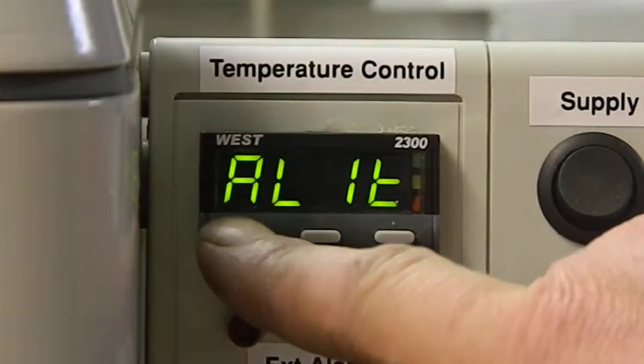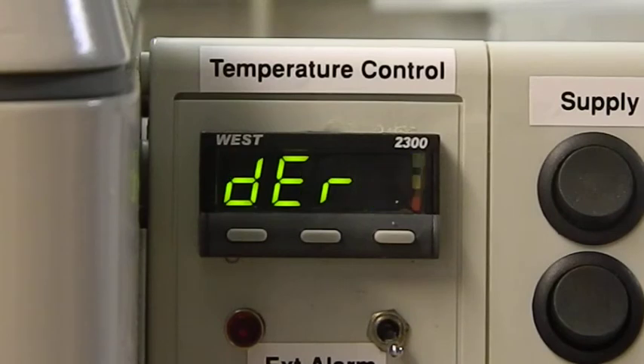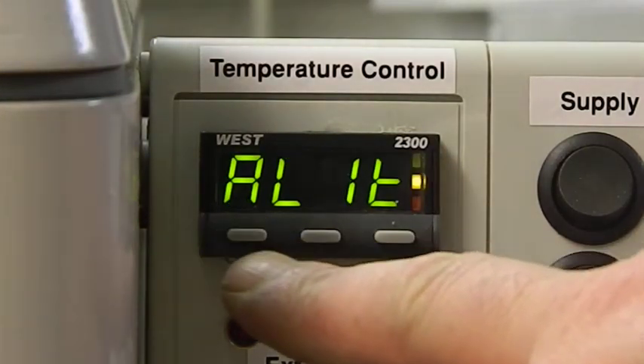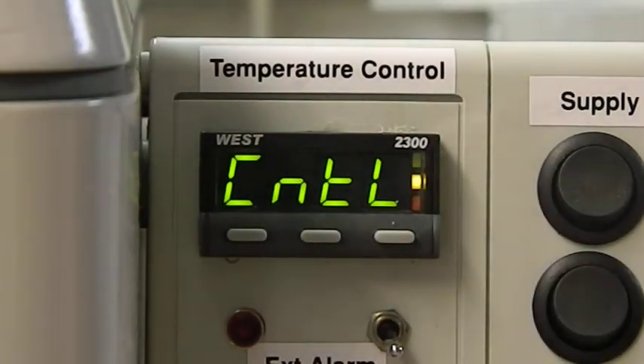So the left one twice again. AL1T. This tells the alarm how it's to function, so this particular setting is deviation, so it's working in relation to the set point. Whatever you change the set point to, the alarm will track with it and stay above.